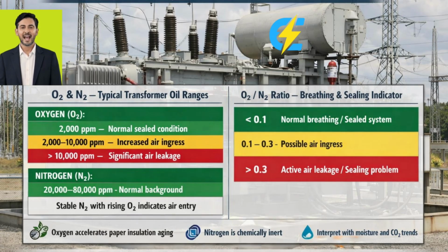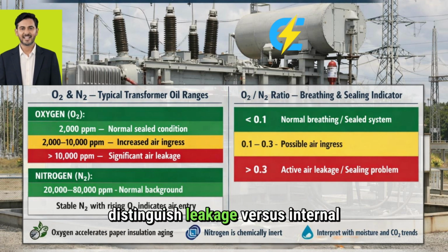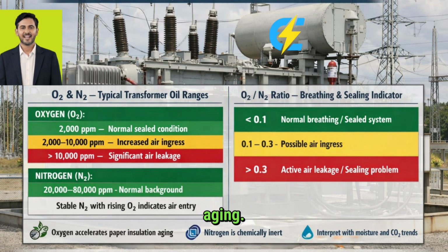However, when you see high oxygen with stable nitrogen, this ratio helps distinguish leakage versus internal aging. If oxygen is being consumed internally while nitrogen remains constant, your O2/N2 ratio will decrease. This is a chemical aging warning. Your transformer oil is actively oxidizing, consuming oxygen in the process.